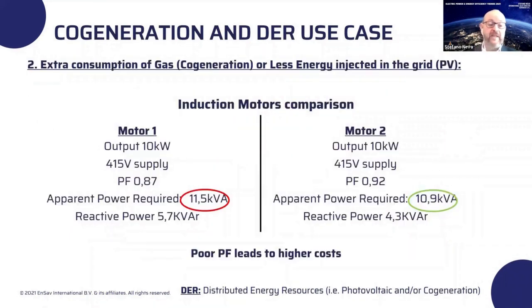Another problem they are facing is that a poor power factor leads to extra consumption of gas, because they have a lot of big cogeneration plants. They need to create more kVA, the apparent power required to run their motors. Because of their poor power factor, they need a lot of kVA, which means a lot of gas, and they need to run these motors at full speed to provide active power to the motors.